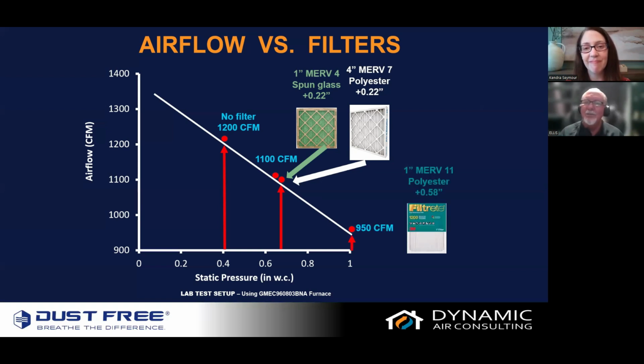So let's move on. We're going to go to everybody's favorite, the 1-inch MERV. I can't see what it is. I think it's a MERV 11, polyester. Its static resistance is 0.58, off the charts. It now brought our CFM down to 950. This is the one you get at the big box store. They call it the allergy buster. It's a 3M, and I will say this, I have tested these for particulate removal. They are fantastic, but they are giant slayers, and they will slay your system if they're not designed in properly.